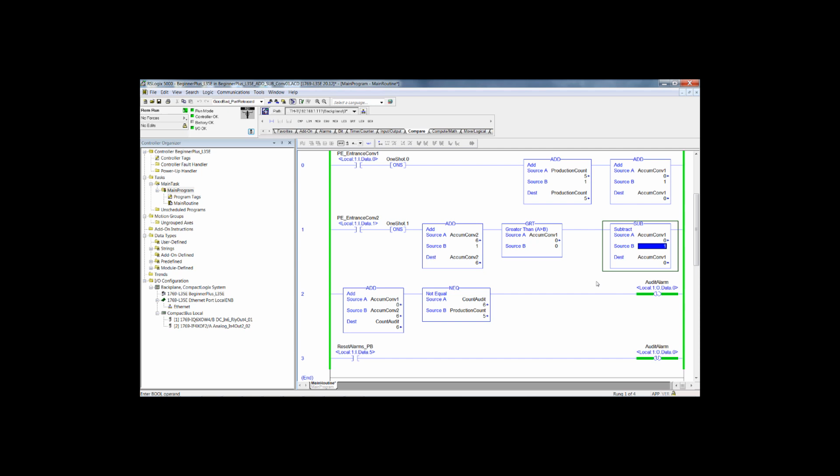We did have a miscount, but the miscount did not trigger the audit alarm because we created a negative number on conveyor 1. -1 plus 6 equals 5. So the production count did match the total number of cartons when you added the cartons on conveyor 1 and conveyor 2 added together. Now this logic functions. We added a comparison function to prevent decrementing conveyor 1 count below 0.